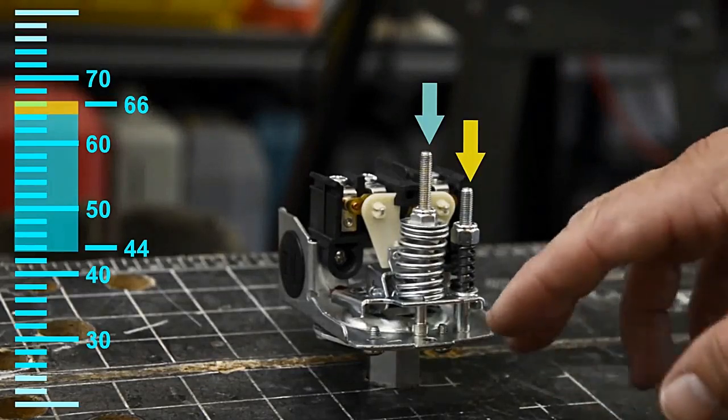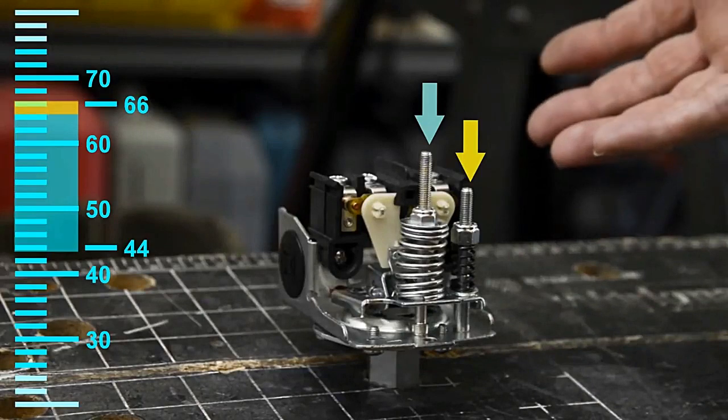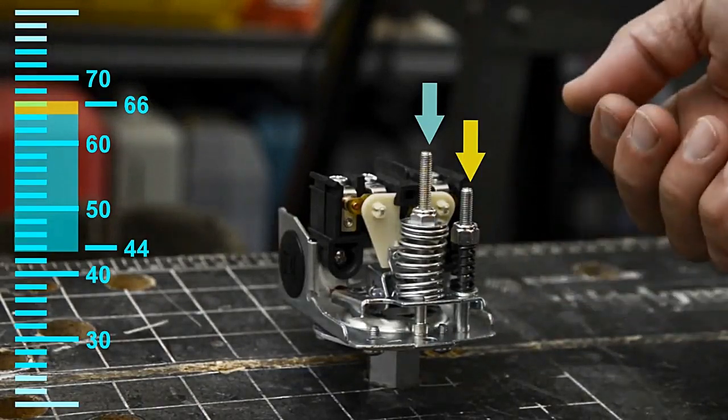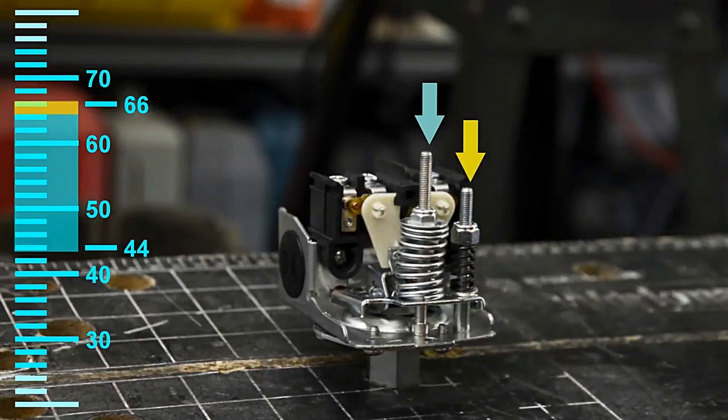The reasons it could go out of adjustment is because these are metal springs and depending on the temperature and also the age of the pressure switch, they tend to change their value and you would have to readjust the pressure switch.